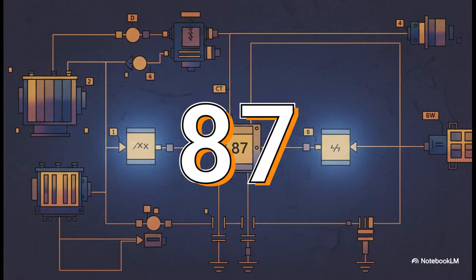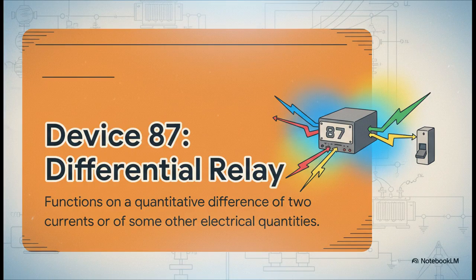All right, now for one of the most ingenious, most clever protectors in the whole system. Let's talk about the differential relay, device 87. This one is just brilliant. An 87 relay is usually used to protect one specific, very expensive piece of equipment, like a huge power transformer.